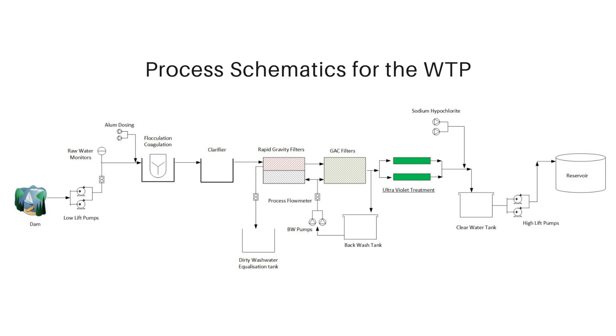The difference between these two filter types is that the rapid gravity filters are our primary filters, which focus mainly on turbidity removal. The GAC filters focus on removal of organic compounds in the water. From the GAC filter, the water passes through UV reactors where it is disinfected using ultraviolet treatment. That UV process is our primary disinfection. Once the water is disinfected by UV it then flows to the clear water tank.